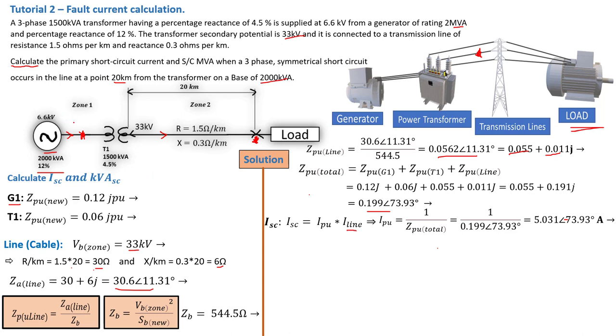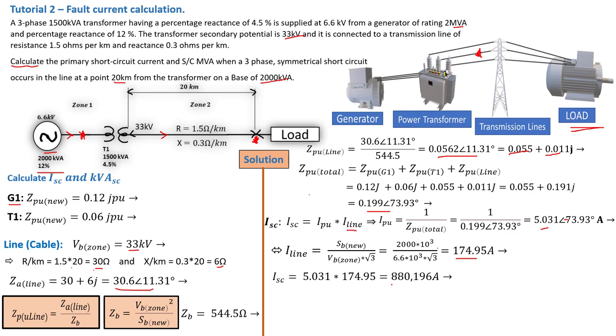For the primary side, the zone voltage is 6.6 kV. I line = SB new / VB zone = 2 MVA / 6.6 kV, giving I line = 174.95 amps. Multiplying I per unit by I line, we get the short circuit current = 880.2 amps on the primary side of the transformer.